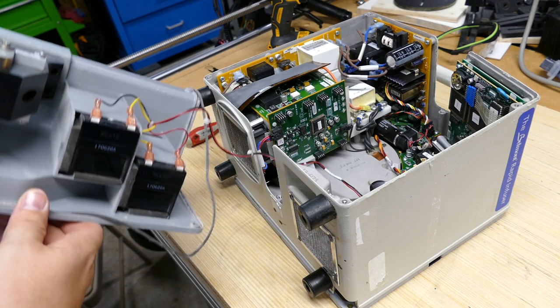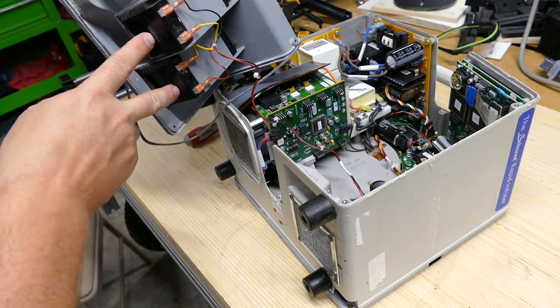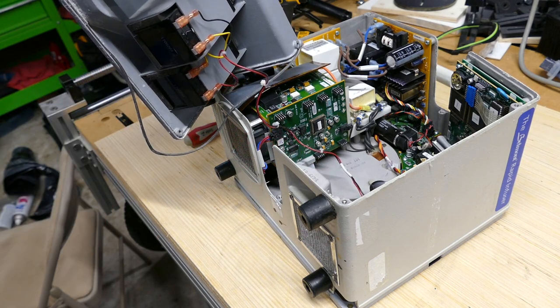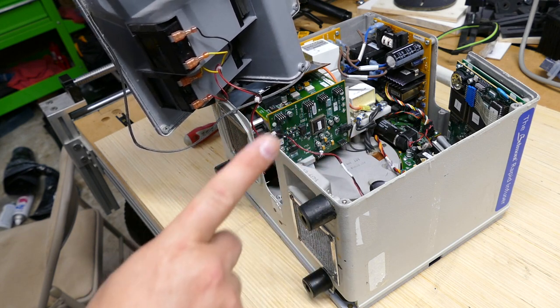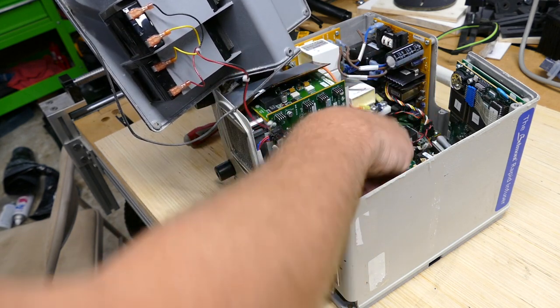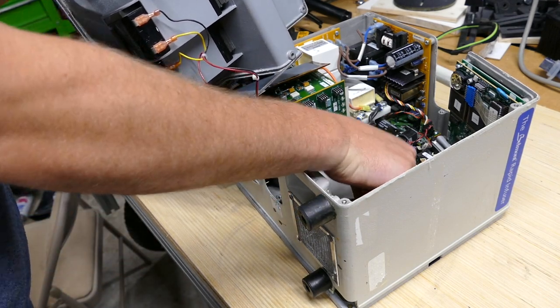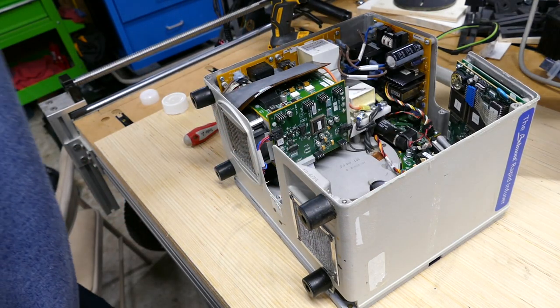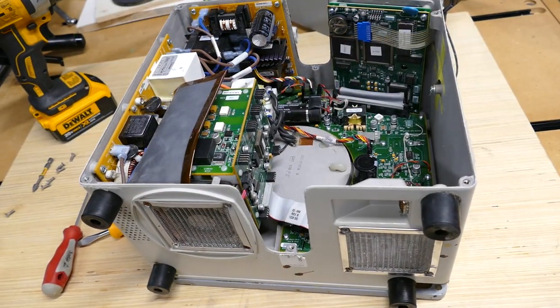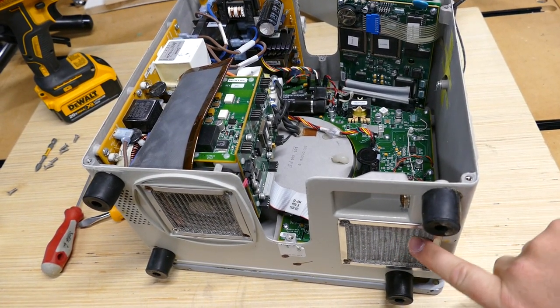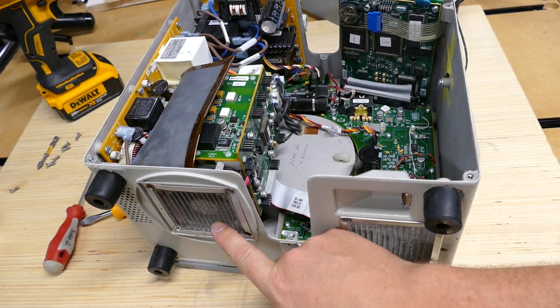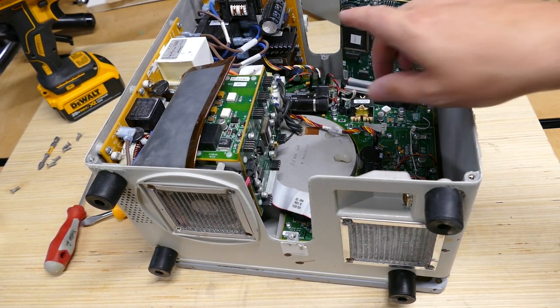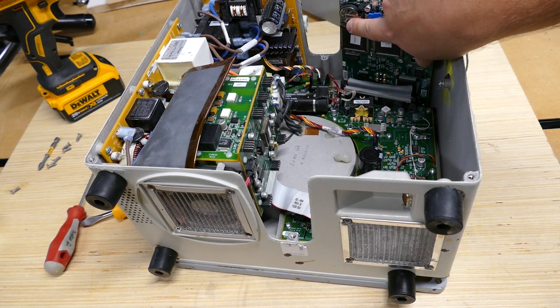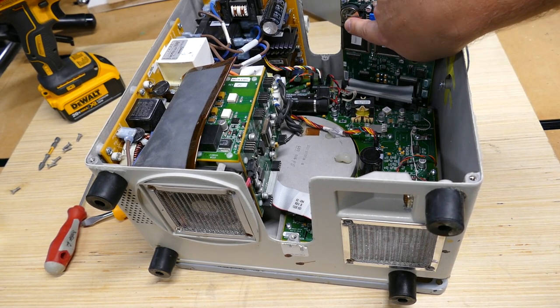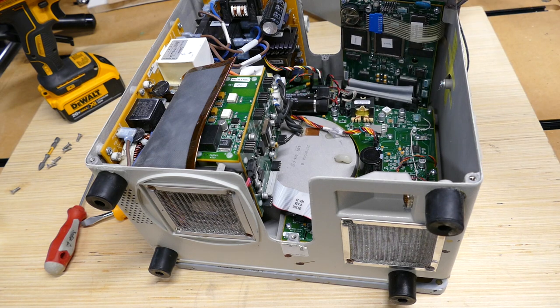The most important part of the inside of this device are these guys right here. These are your lead acid batteries. Remember, they have to be changed every 3 years. So I'm gonna go ahead and disconnect the batteries. Place the cover off to the side. Some points of detail are gonna be your filter screens right here. These guys need to be cleaned with every PM. And then on the inside, the other thing that you have to take notice of is a coin cell battery. This guy is probably going to have to be changed about once every 5 years. That's going to maintain your settings. Make sure your software doesn't get corrupted.